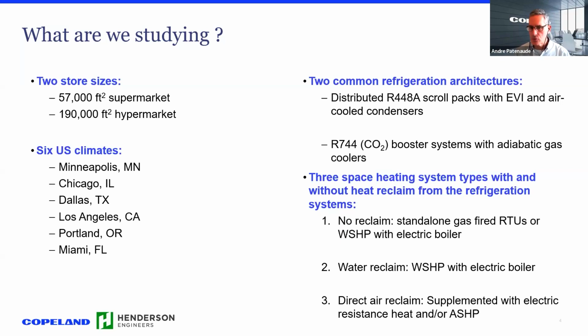And then the 2 refrigeration architectures we looked at were distributed 448A scroll packs with enhanced vapor injection. Enhanced vapor injection provides subcooling to the liquid. So that's an advantage. So we wanted to make sure we captured that because it's popular. And then, of course, your CO2 booster systems, but with adiabatic gas cooler. We did not do dry gas cooler because the majority of CO2 systems out there are being installed with adiabatic. So that's what we decided to use as our baseline.